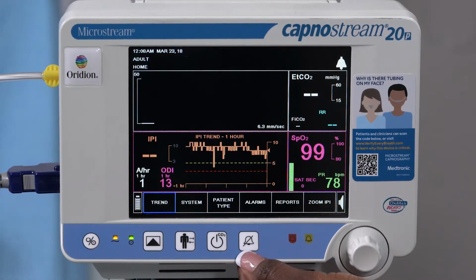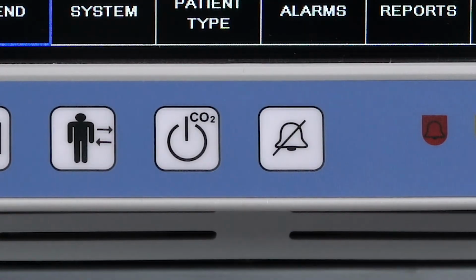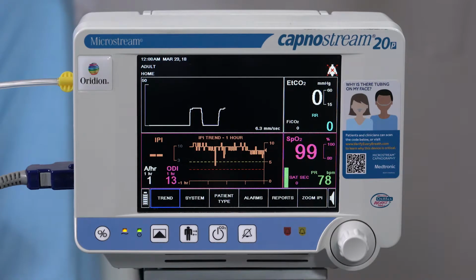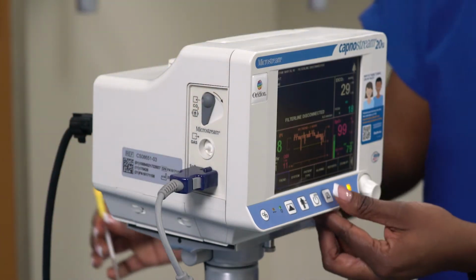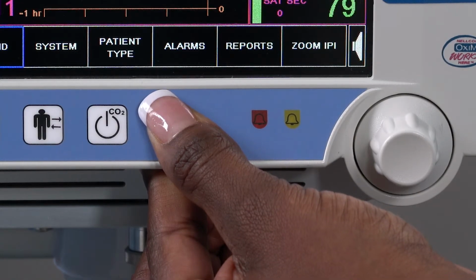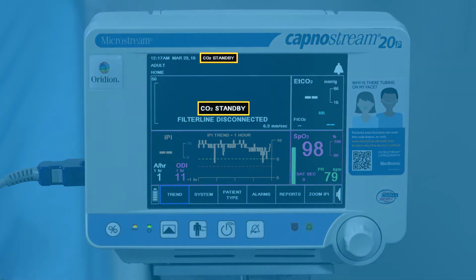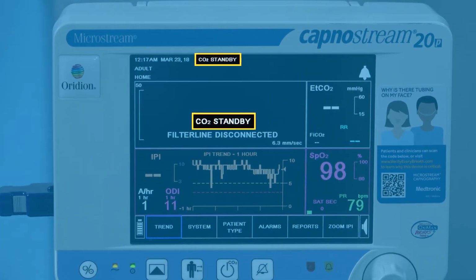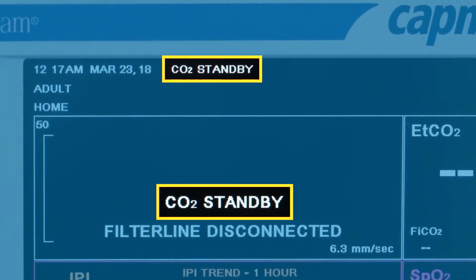Temporary alarm silence button. Pressing this alarm silence button will suppress any audible alarms for 2 minutes. To end the alarm silence, press the button again. For CO2 standby mode, remove the sampling line from the monitor. Then press the alarm silence button for 2 seconds or longer. A standby message will now appear on the monitor. If the standby mode has not been enabled in institutional default settings, the monitor will automatically go into standby mode when a sampling line or SpO2 sensor is detached.